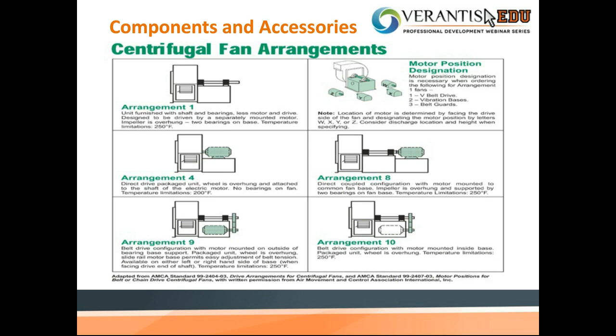Arrangement 9 is where the motor is attached to the base. It can be on either the left-hand side or the right-hand side. Usually the motor sits on an adjustable base to properly tension the belts. In arrangement 10, the motor is actually inside of the base, and it sits on an adjustment plate. There are obviously limitations with an arrangement 10 based off the motor size, and that's typically when we change to an arrangement 9 or a 1 style, where the motor is off on a separate pedestal.